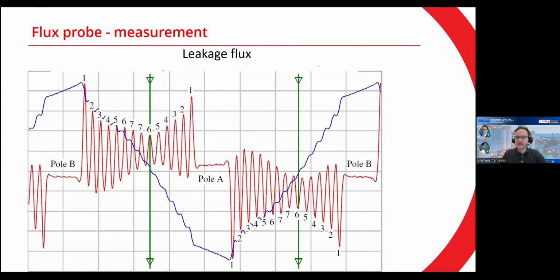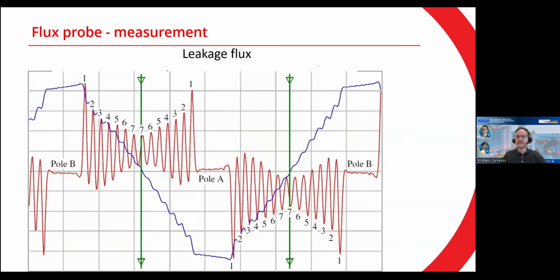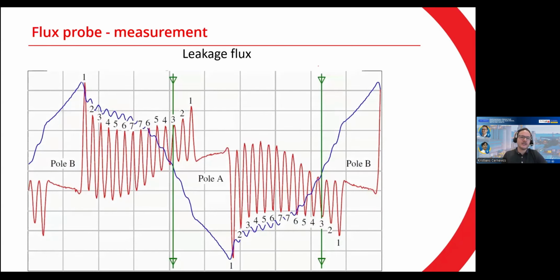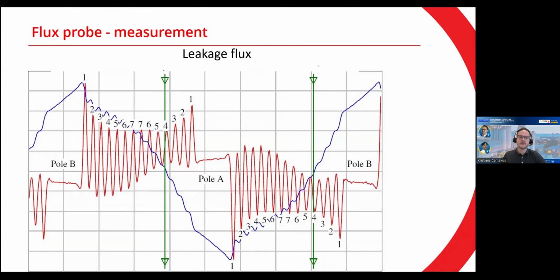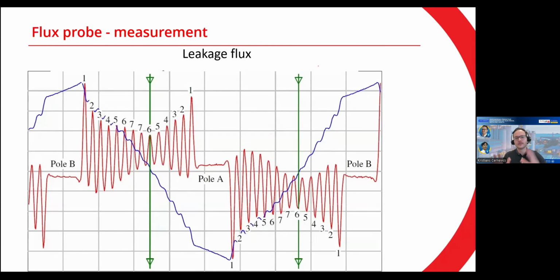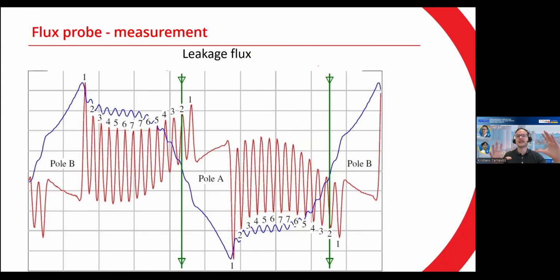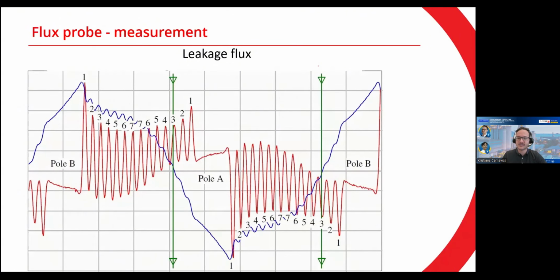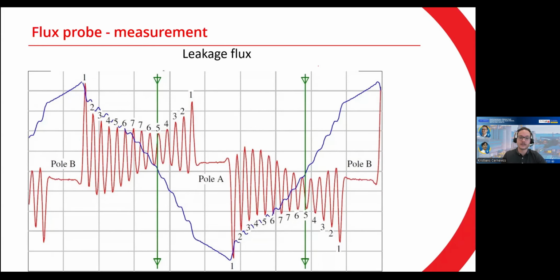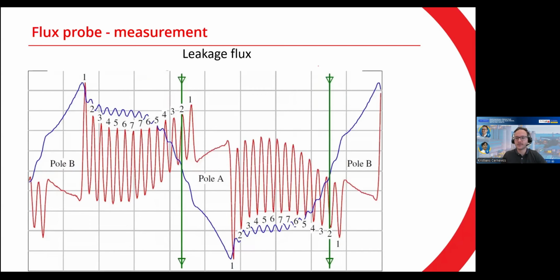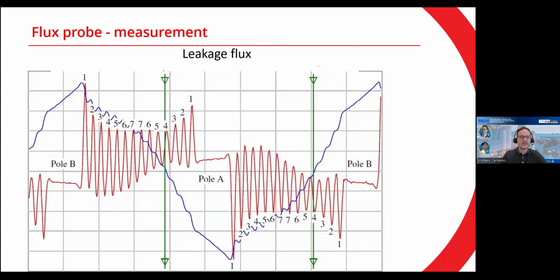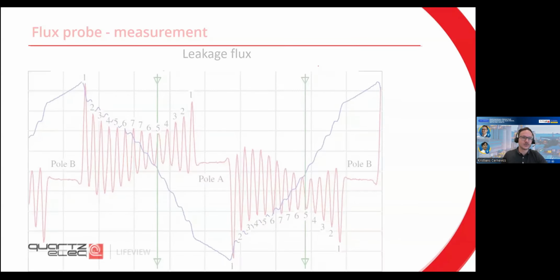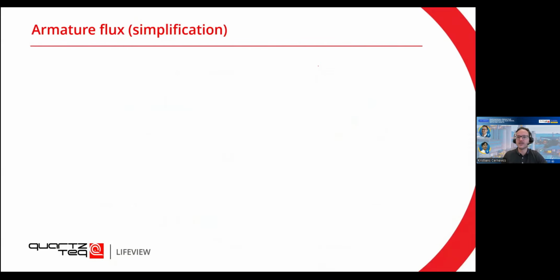At different load points, different coils will be more sensitive to make the measurement. What happens here is that you just compare the coils from one pole, from one side, to the coils of the other side, and you compare if the difference in the voltage or in the flux is high. If there is a high difference, it most likely means that there is a short. And to explain a bit about the sensitivity of these measurements, bear with me here, it's a bit technical, a bit of engineering.